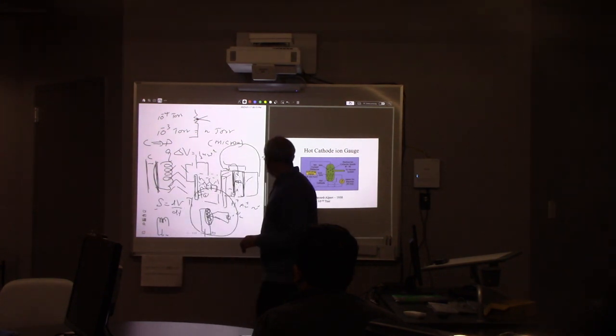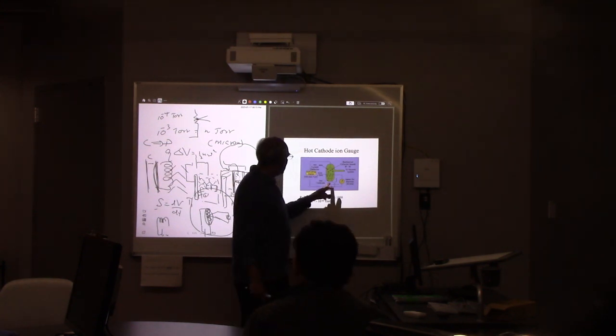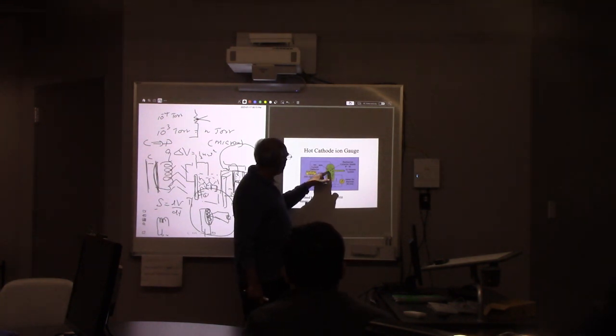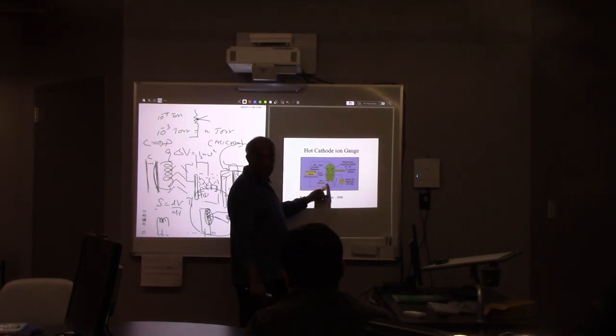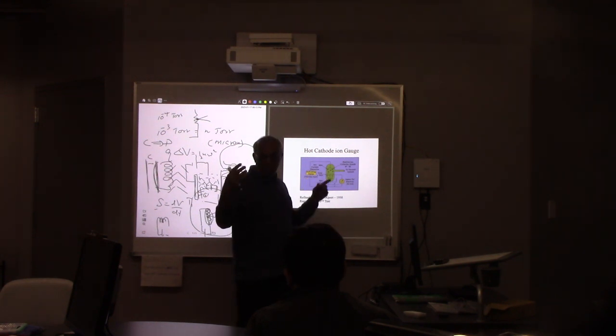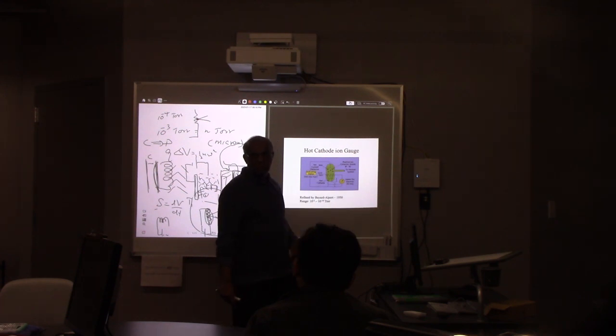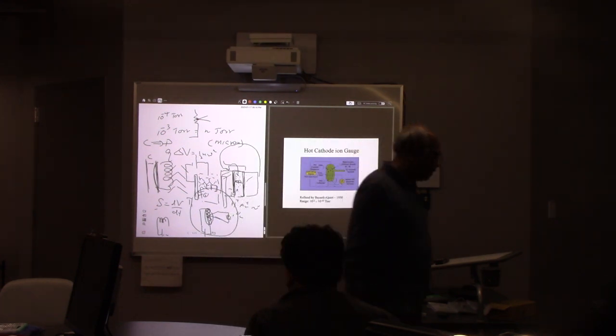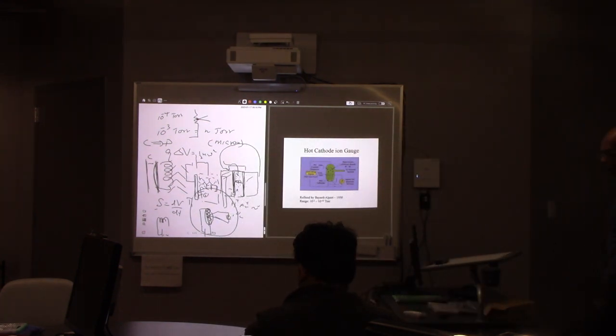So here we are talking about thermionic emission. By heating this, you emit electrons, so they will ionize the charges. Then these charges will be attracted to the anode and cathode, so you can just measure the current. So the current depends on the vacuum, right? If you have fewer particles, if it is really clean, the current goes really low, because there are no charges to pass through here. That's the basic mechanism of the hot cathode gauge.